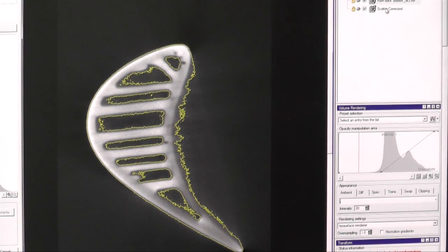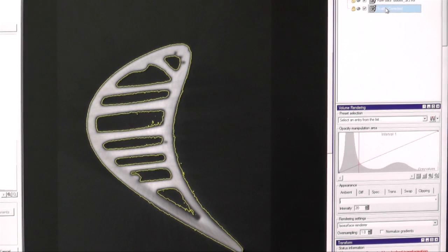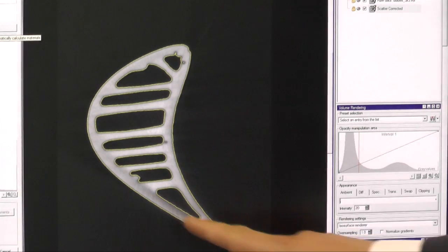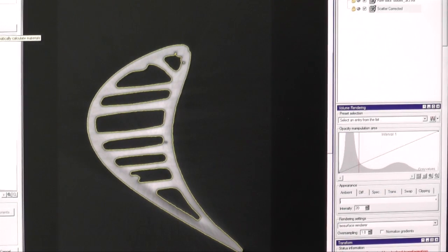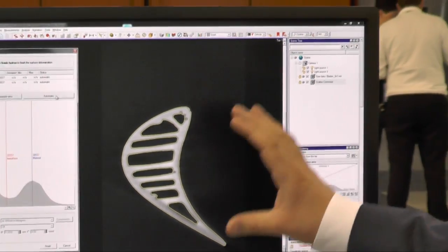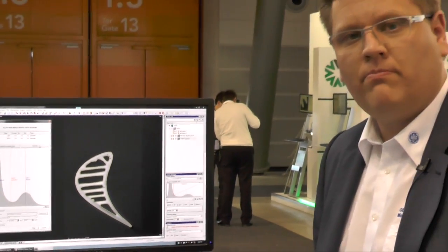When doing the same scan with the same X-ray source and the same detector, but now using GE ScatterCorrect, I get to this result. When applying the automatic surface detection, you can see how well defined the surface is now detected. That allows precise measurement of highly accurate small thicknesses, especially at higher density parts or materials of larger material thicknesses.